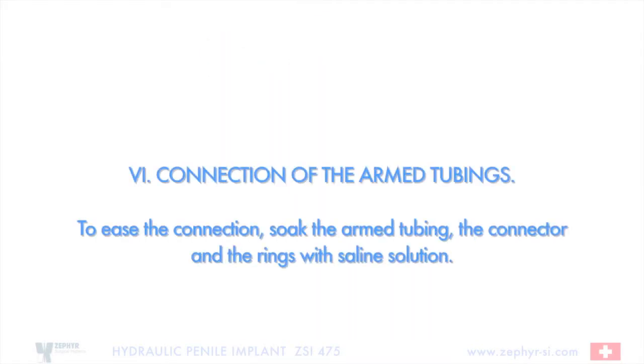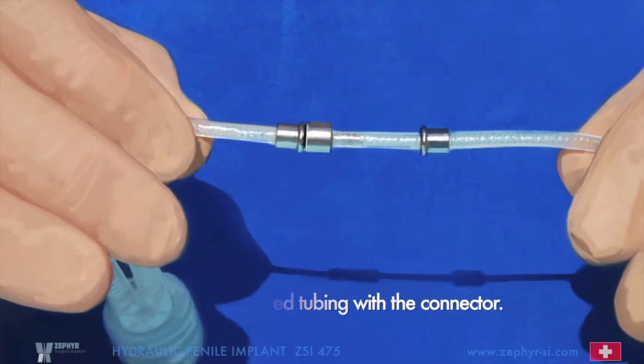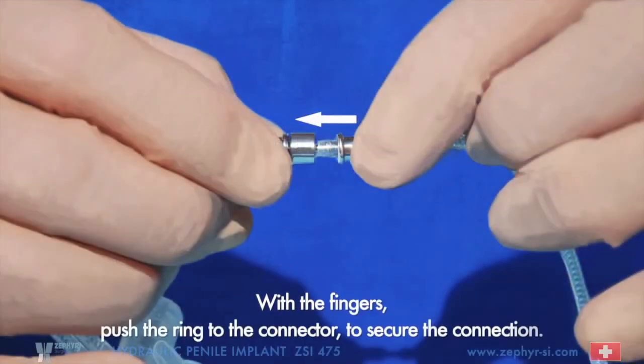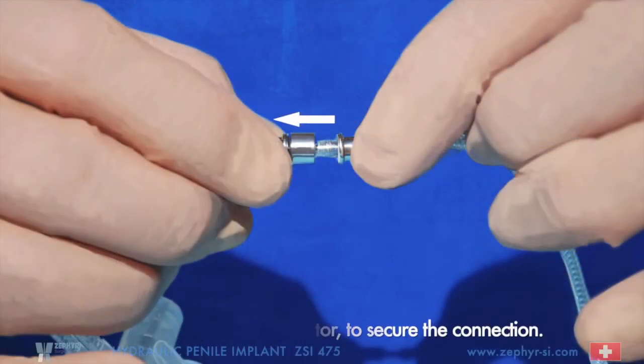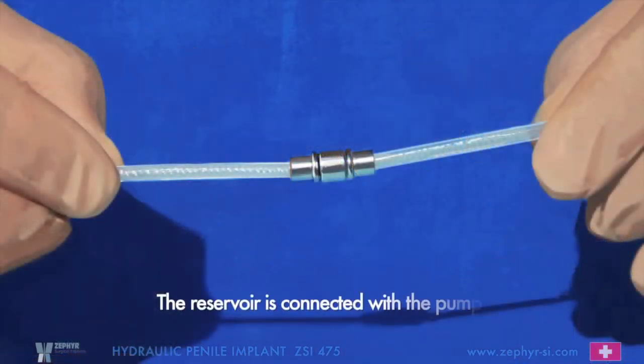6. Connection of the armed tubings. To ease the connection, soak the armed tubing, the connector, and the rings with saline solution. Connect the armed tubing with the connector. With the fingers, push the ring to the connector to secure the connection. The reservoir is connected with the pump.